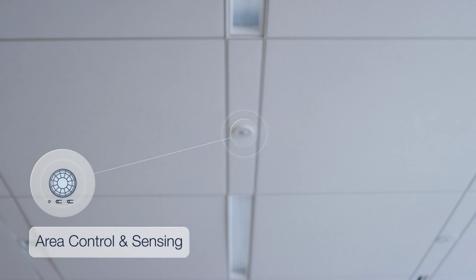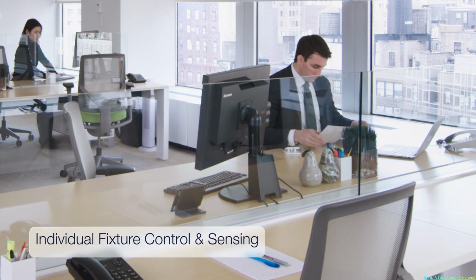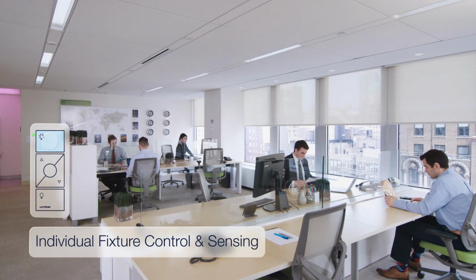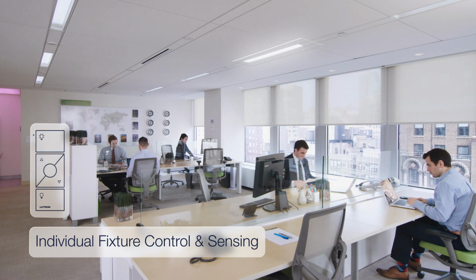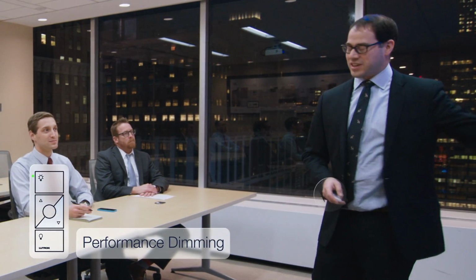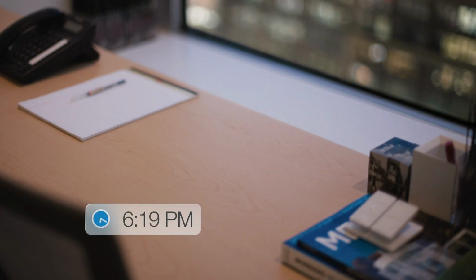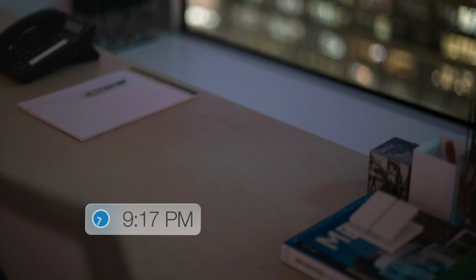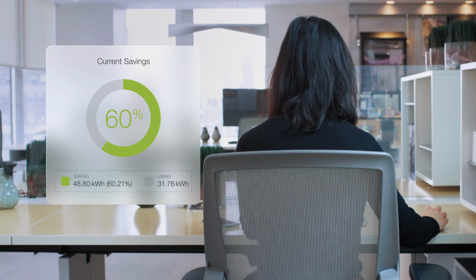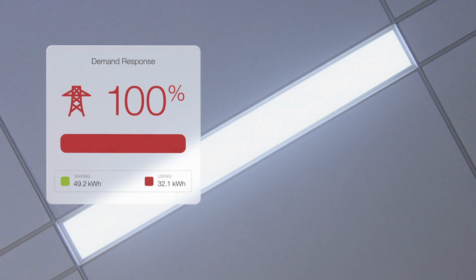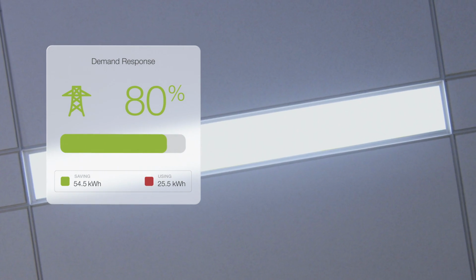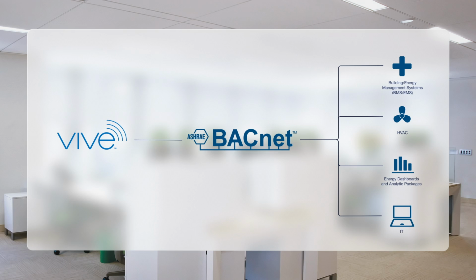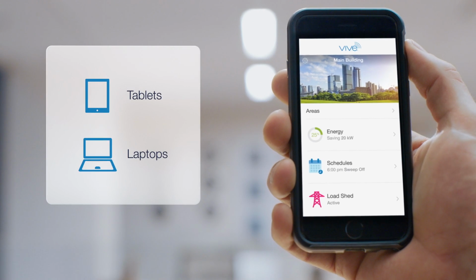Wireless controls allow you to design options that provide the right functionality for each space in your building. Vive is simple enough to deliver basic energy savings and robust enough to apply additional lighting control strategies, such as time clock scheduling, energy and system monitoring, demand response load shed, and seamless integration to BMS via BACnet with software that works on any smart device.